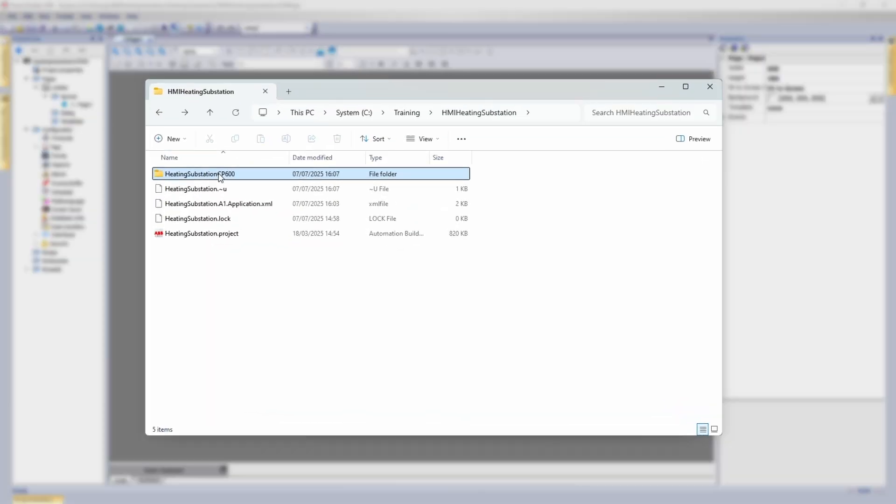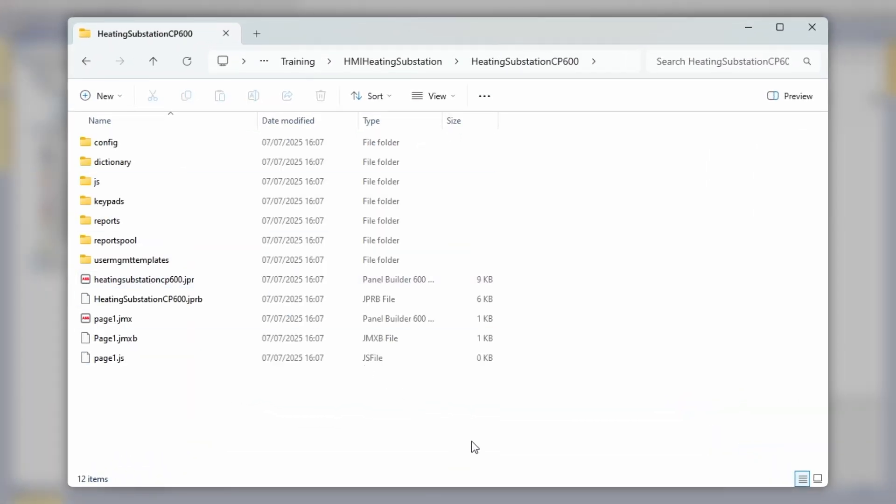Leave the project template with the default value and click Finish. The software will create all the necessary project structure, which will be reflected in the project folder. All these folders and files are your HMI project. If we had created the HMI project from Automation Builder, then each time you open the HMI part, the software would unpack necessary files into a temporary location, and when you close it, pack it again and attach it to the PLC project. Now let's create a communication link between the panel and the PLC.